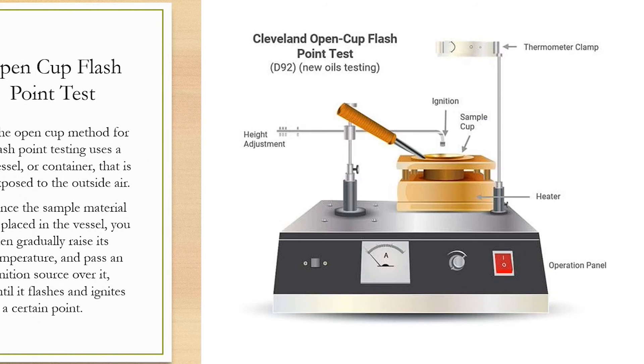Open cup flashpoint test: the open cup method for flashpoint testing uses a vessel or container that is exposed to the outside air — it is truly open so air can enter the inside. Once the sample material is placed in the vessel, you gradually raise its temperature and pass an ignition source over it until it flashes and ignites at a certain point.